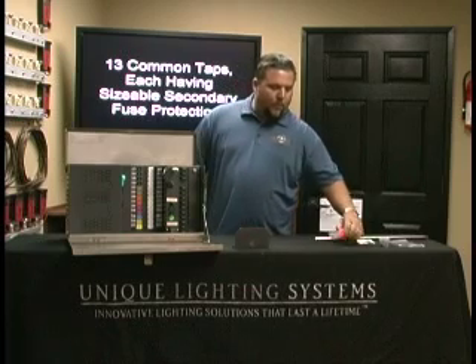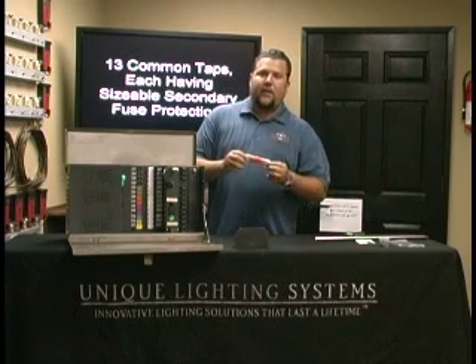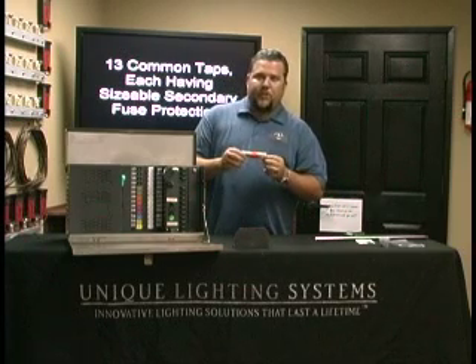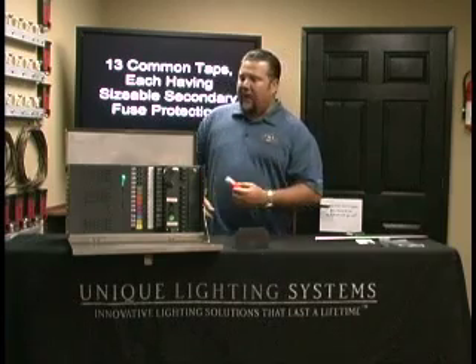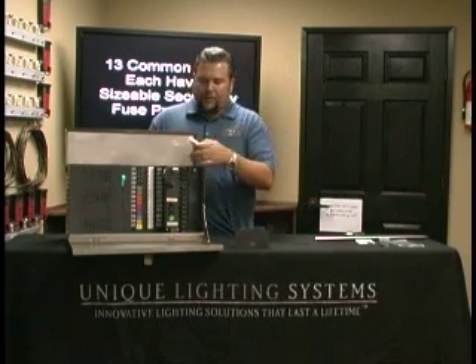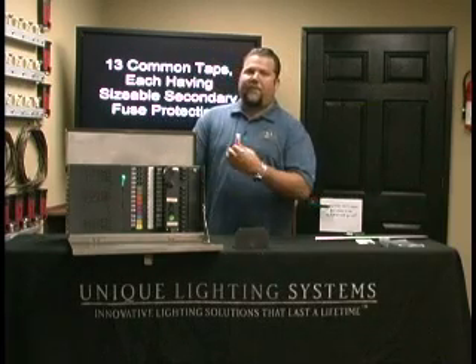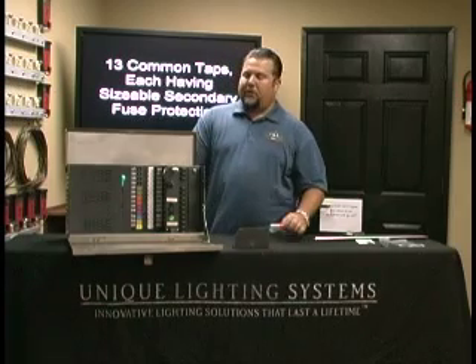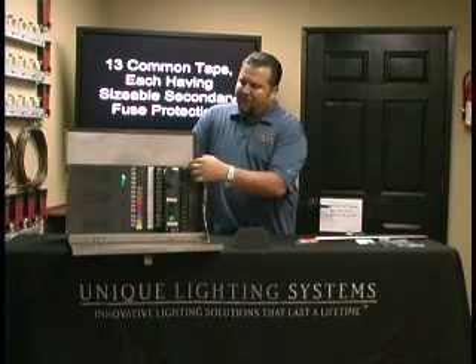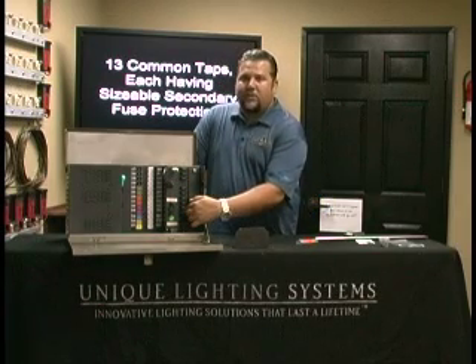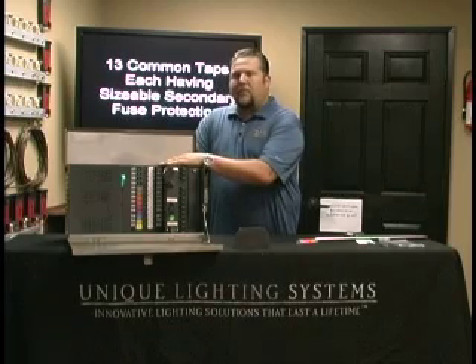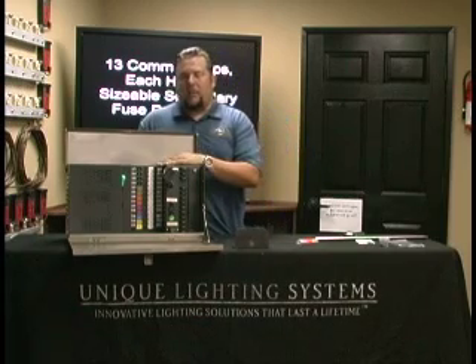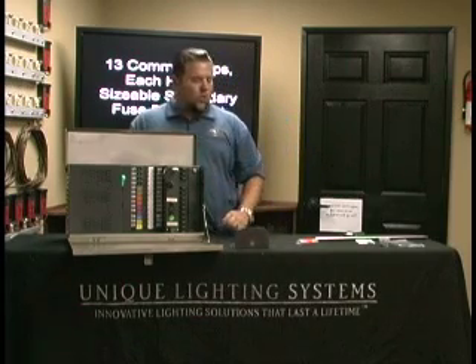The transformer will be provided with an assortment of secondary spade fuses for you to use. So if you've got a 10 amp load, you can put a 15 amp fuse in there. If you've got a 15 amp load, put a 20 amp fuse in. In this case, they're going to come provided standard with 30 amp fuses. So you can load up to the maximum 25 amp per secondary run and be fused accordingly.